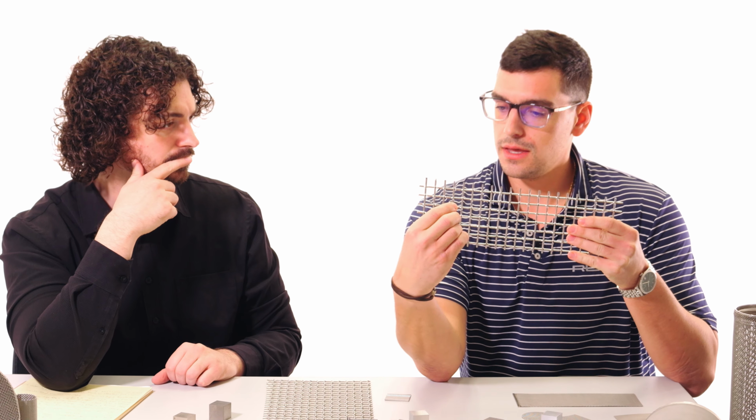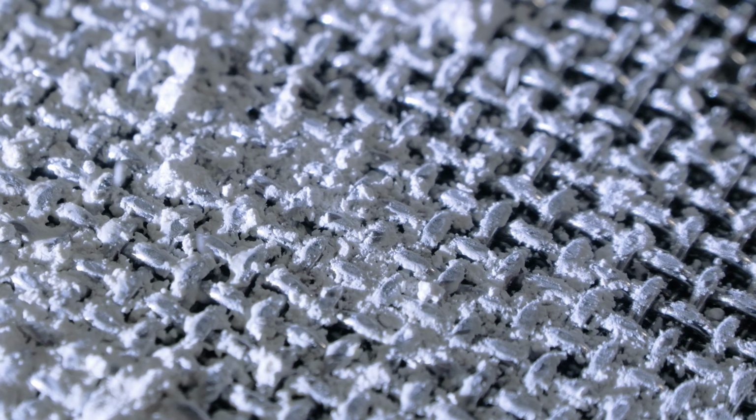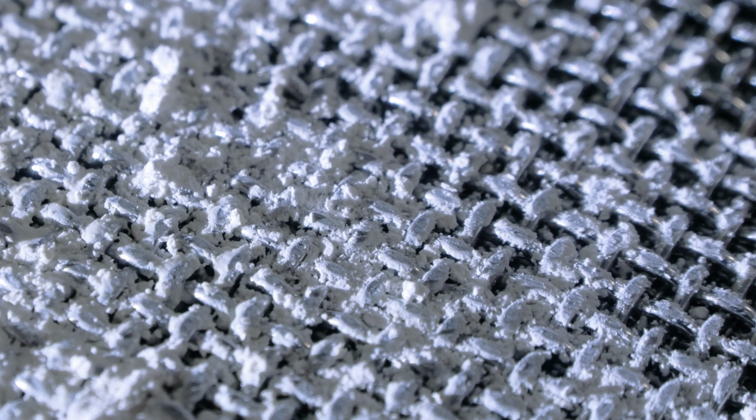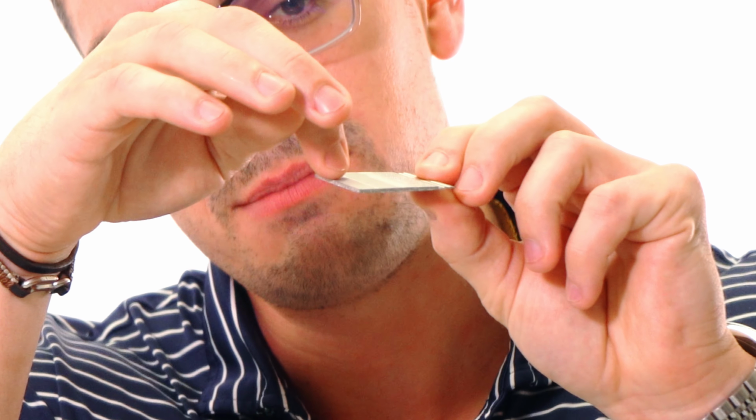So this is our screen, and let's say this is our particle, right? Our particle is coming up to the mesh surface itself, and let's say the particle gets stuck on the wire itself. Like maybe the wire is not smooth, or it has abrasions on it, so it can be kind of sticky. So the particle can get stuck on the edge there itself. Another option is if it comes in at a different angle, it can get stuck inside the actual pore itself. But if it's a multi-layer, it can come through the top surface, swirl around through the different layers and maybe get stuck in the middle. So it can get clogged that way.